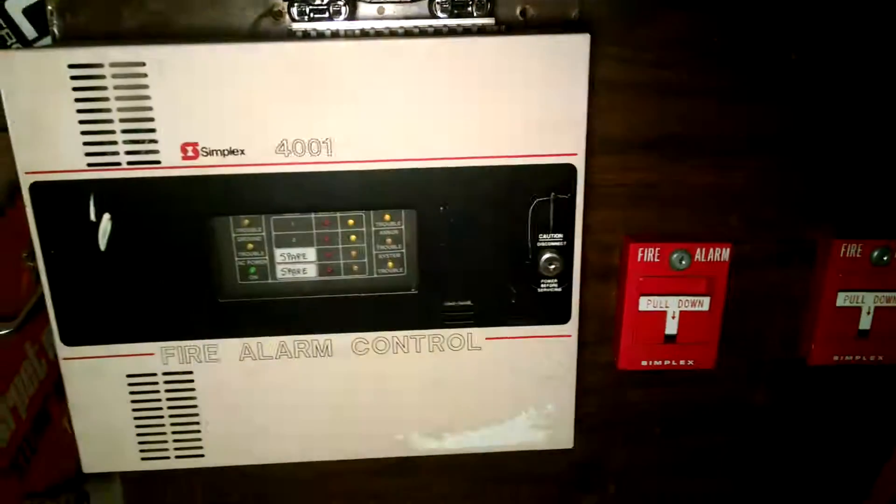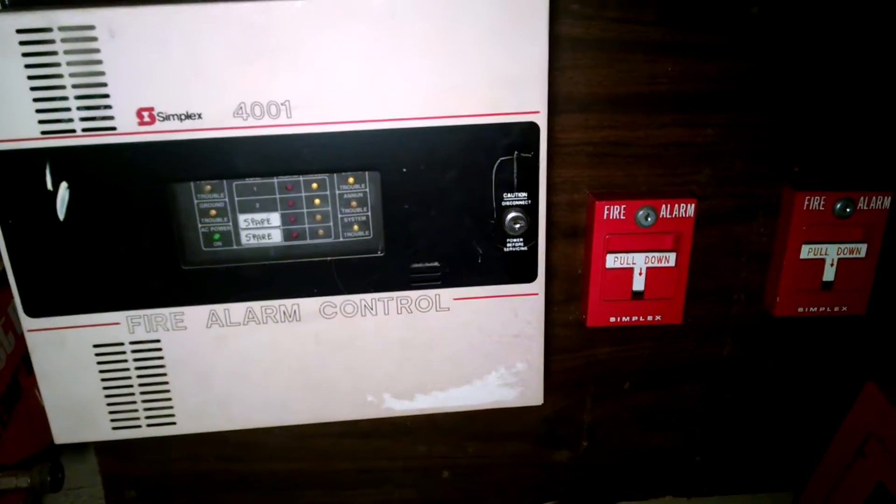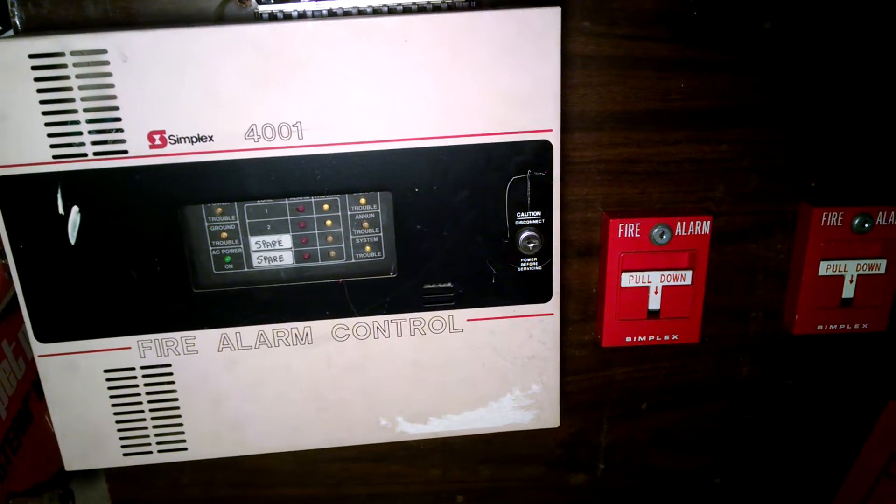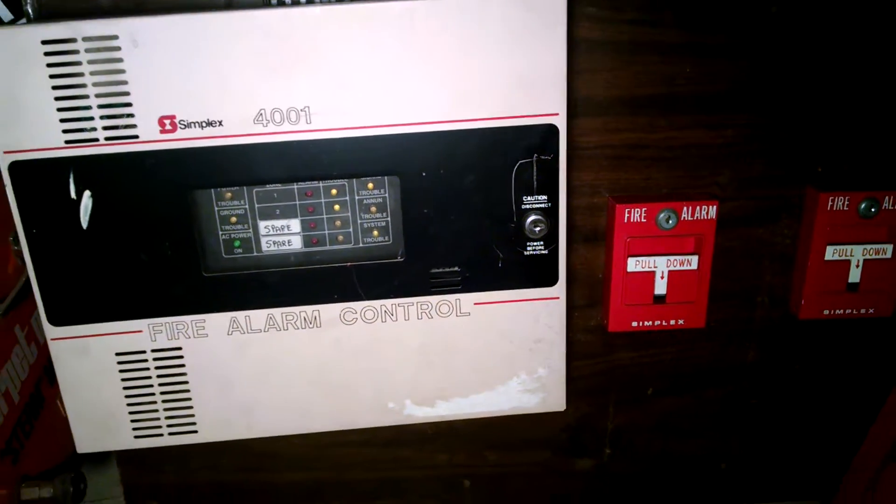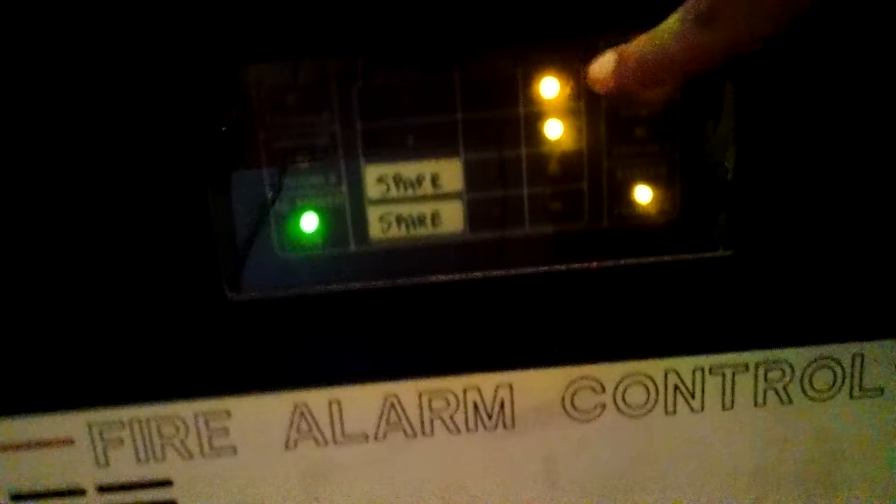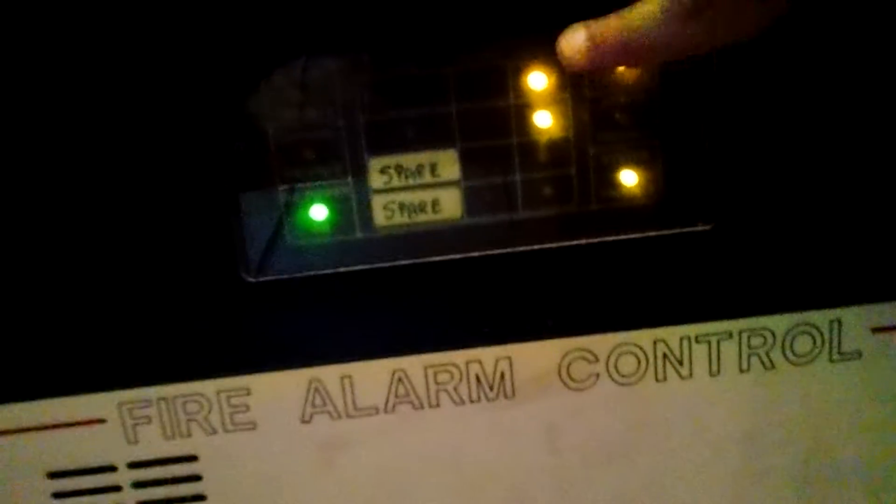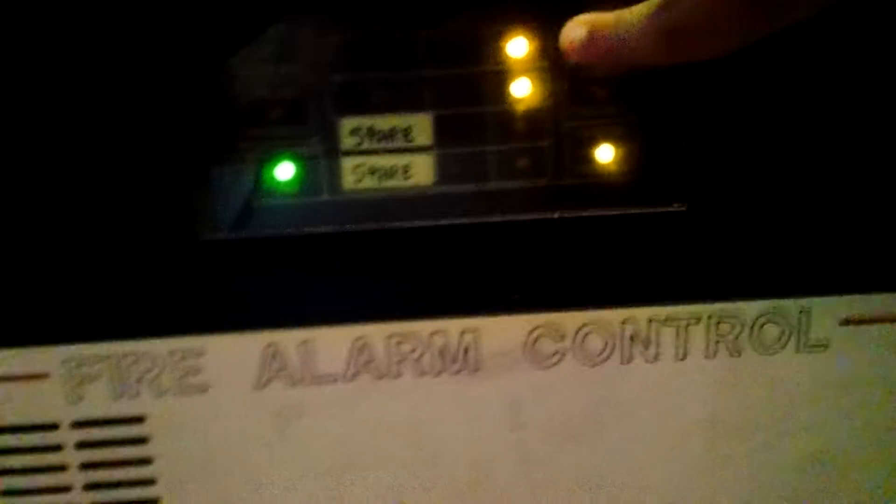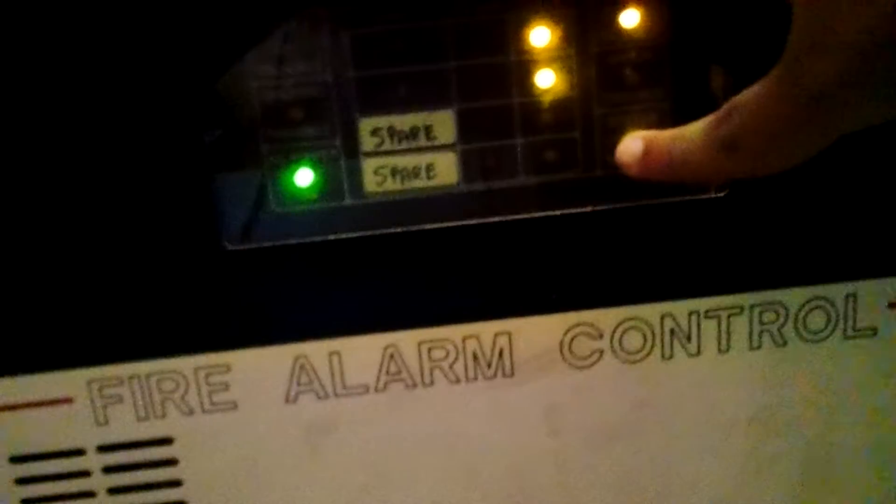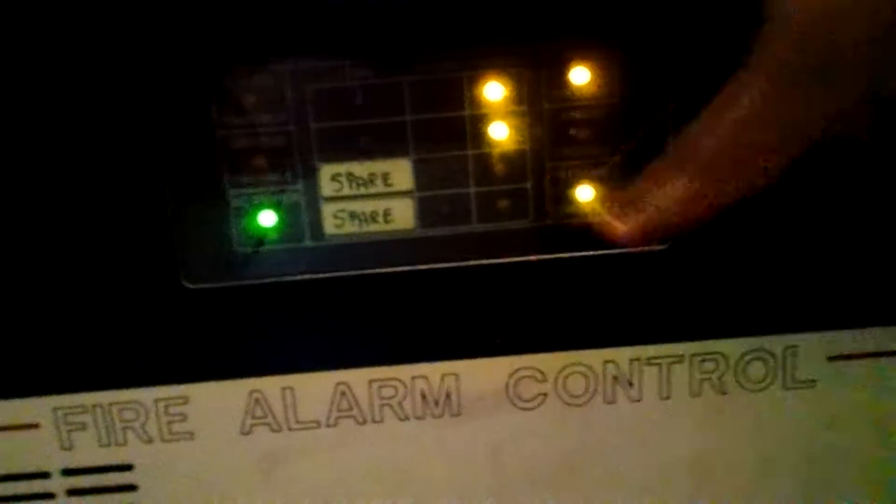As you can see the panel is hooked up and I do have a light back here that I can turn on so you can see it. Now you can see I have troubles on zones 1 and 2 because I don't have resistors on those zones yet. But 3 and 4 do have resistors, so those are not troubled.